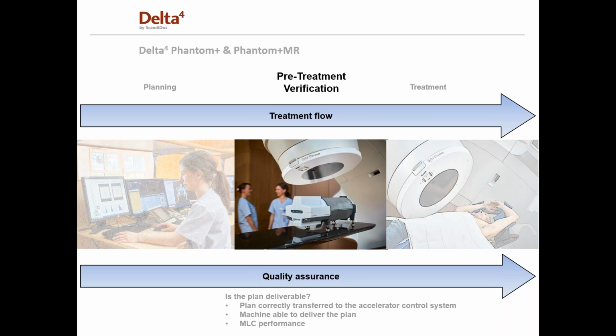So today, we'll be talking about the Phantom Plus and the Phantom+MR, our pre-treatment verification system. So the question comes up, is the plan deliverable? Does it correctly transfer to the accelerator control system? Is the machine able to deliver the plan? And what about the MLC performance?